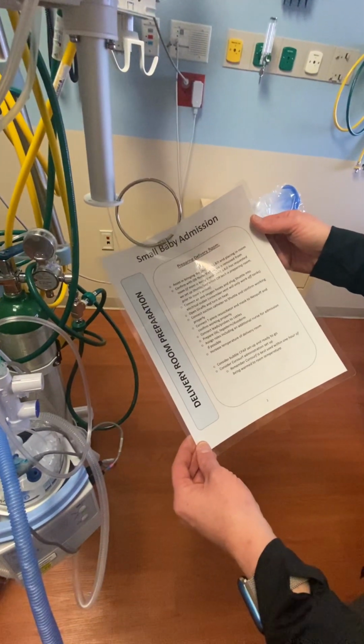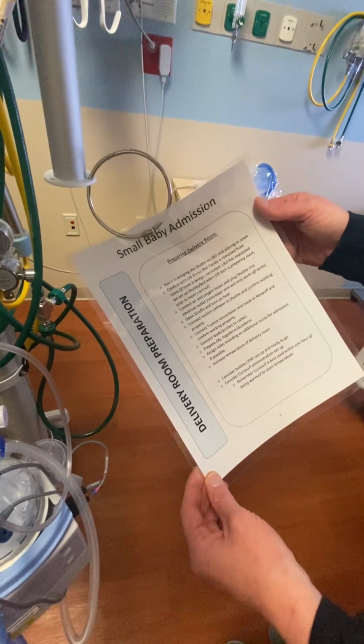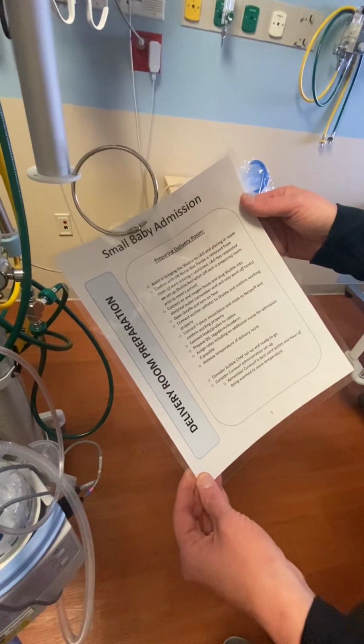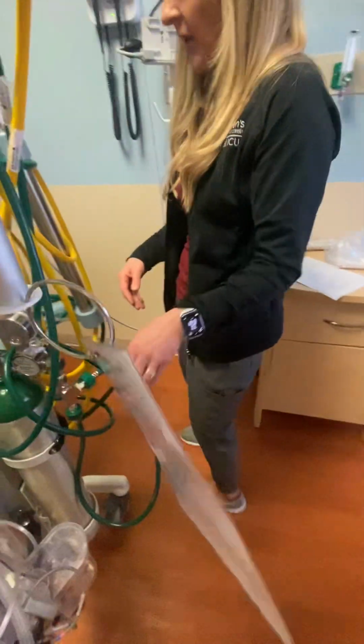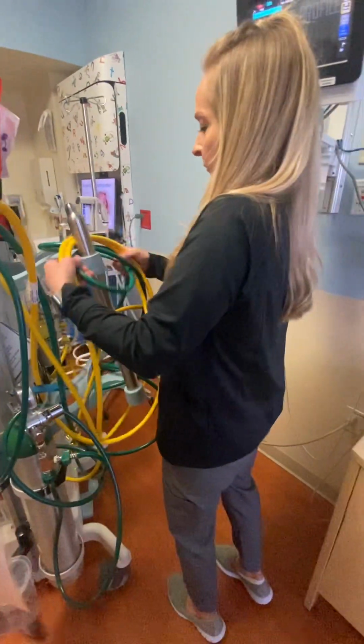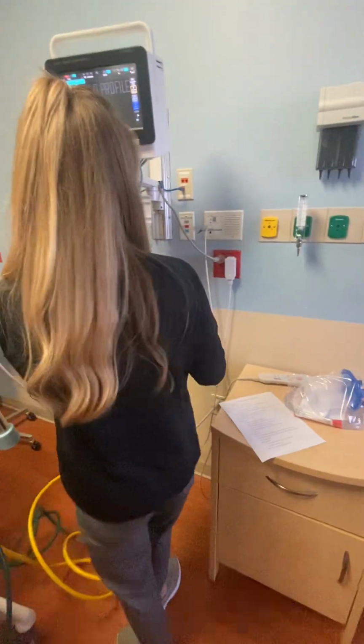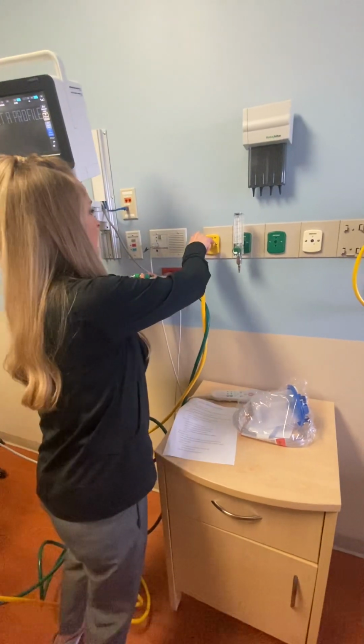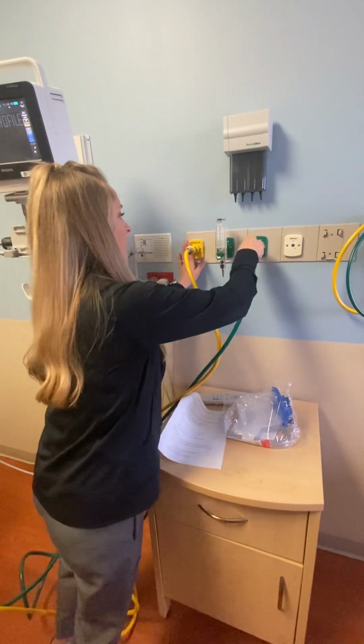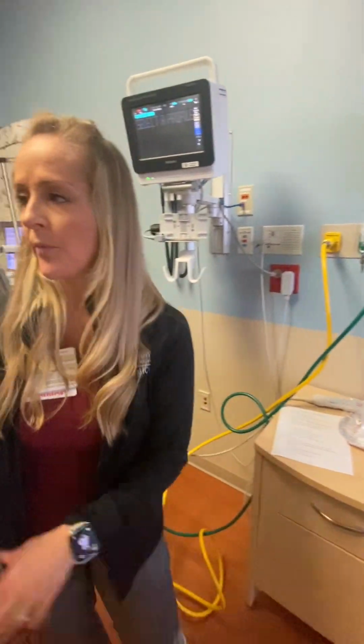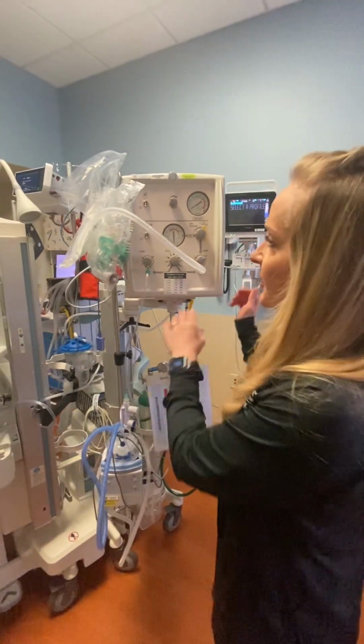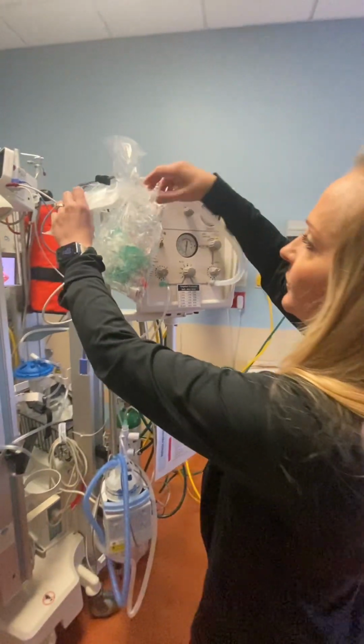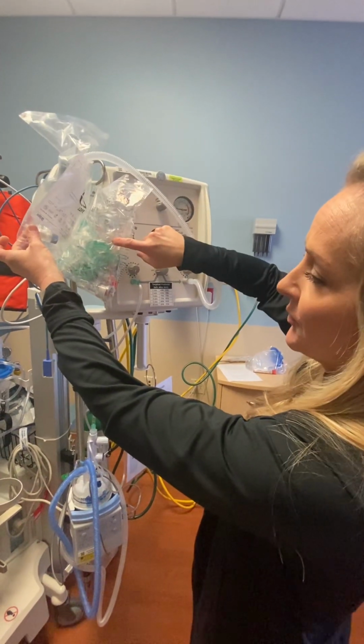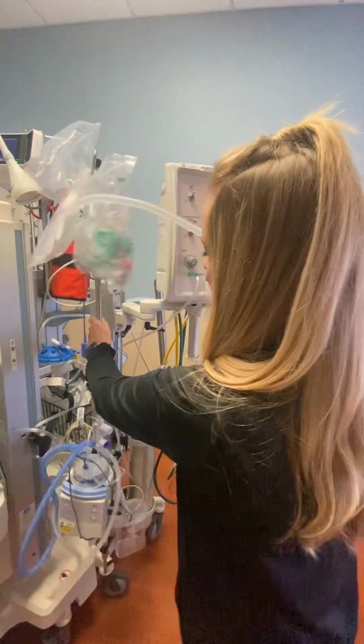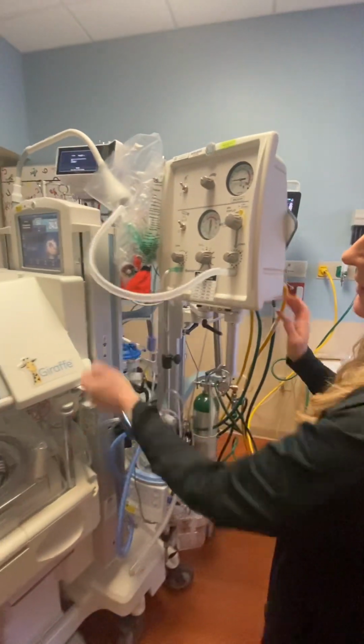So the first conversation that needs to happen with the OB nurse is that they are removing the Panda from the OB room and you're bringing in the Shuttle. Once you get down into the delivery room, you're going to connect your air and oxygen hoses to the wall. And you're going to check all your equipment. You're going to check your T-piece resuscitator, turn on your flows, and set your pressure. Grab your mask, and then you're going to swivel this over closer so it can reach the baby better.